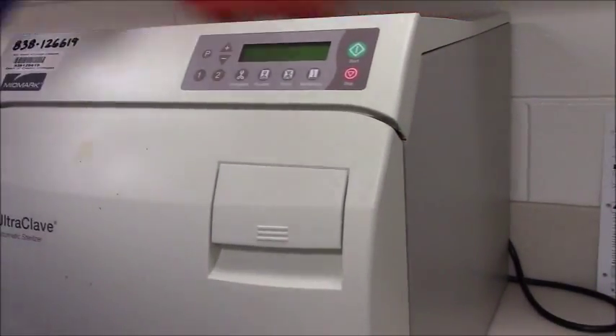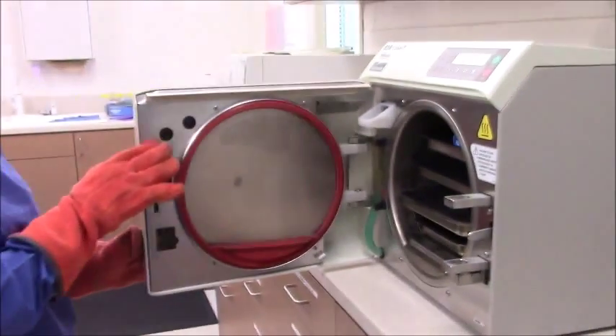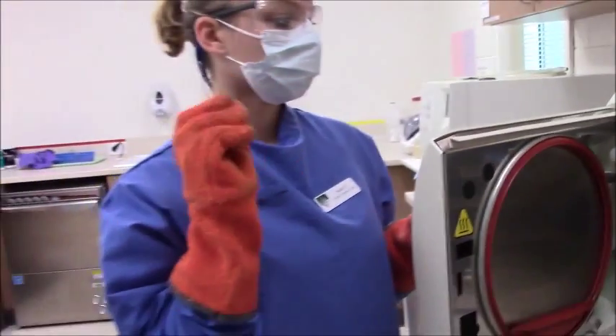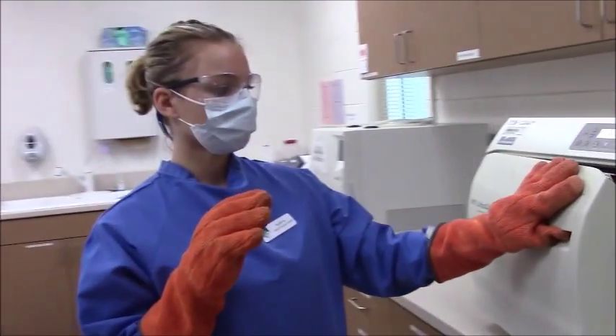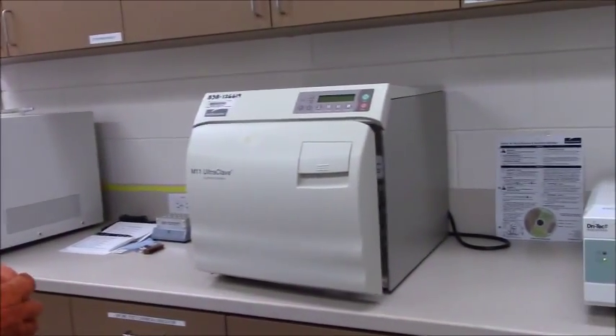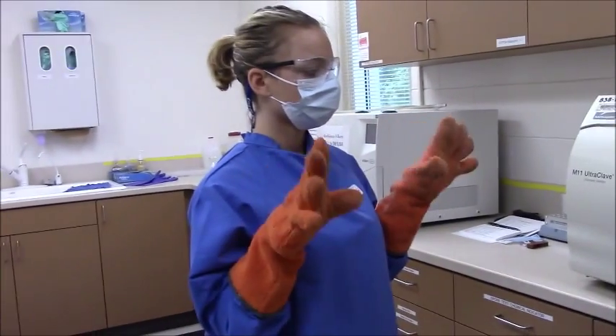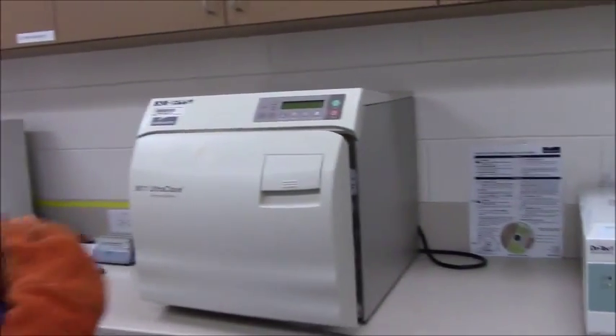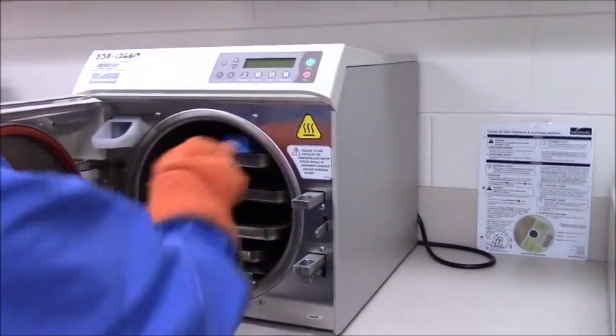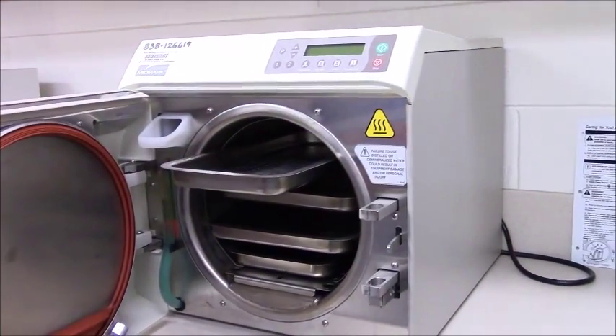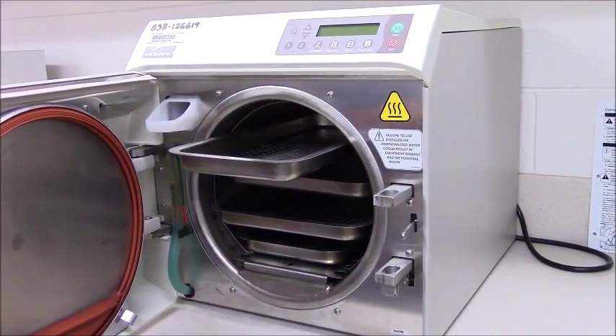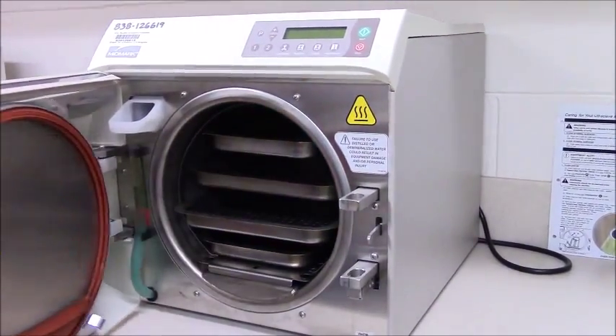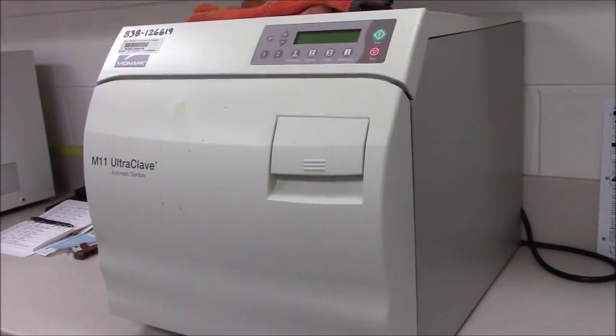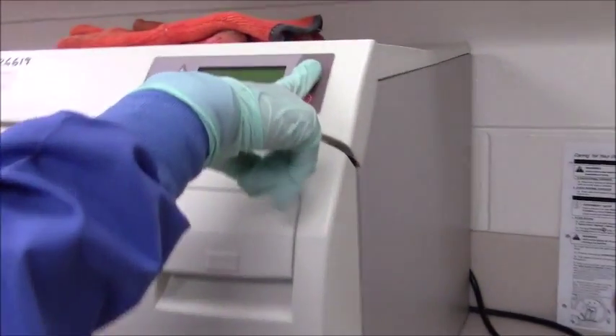After the cycle is done, open the door with heat resistant gloves. Dry and ready lights are flashing until the unit beeps 5 times. Leave the door slightly open until the dry cycle ends. Ready light flashes, unit beeps 5 times. Instruments are now ready to be removed. Turn off at end of day and unplug.